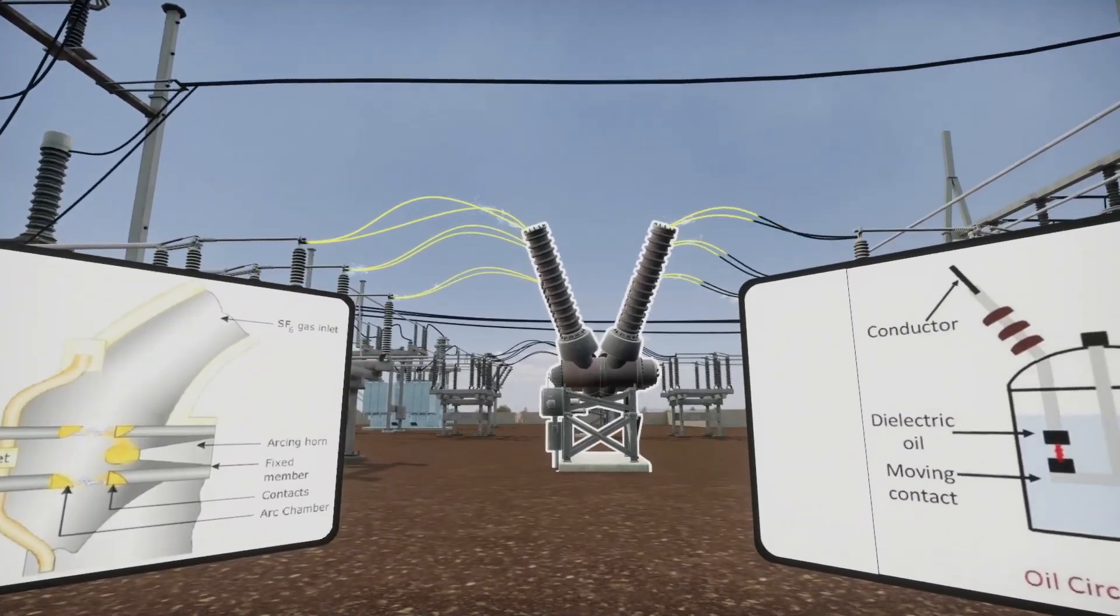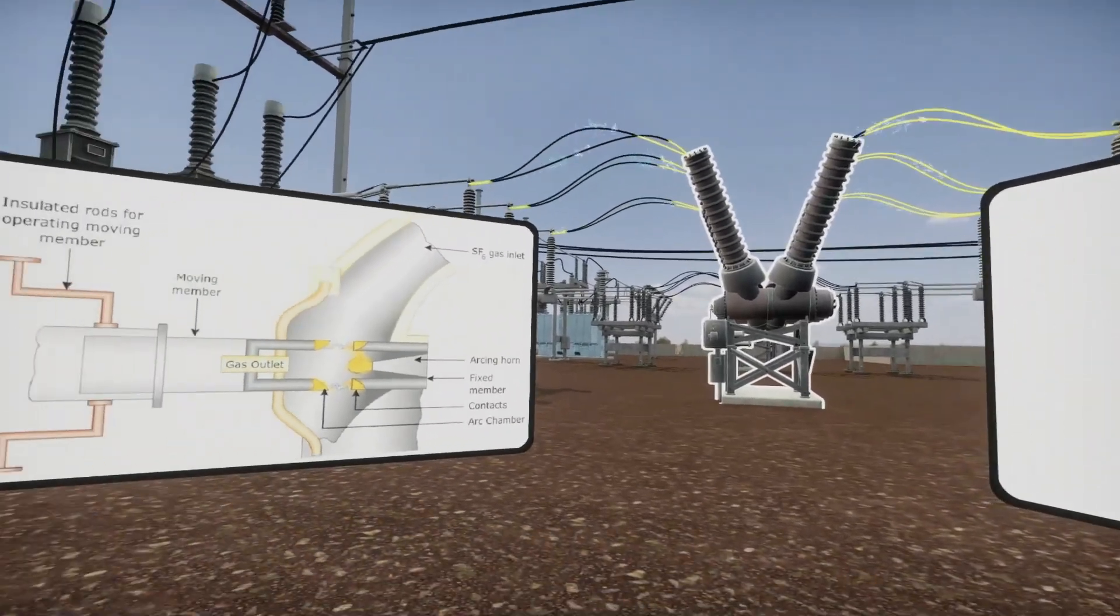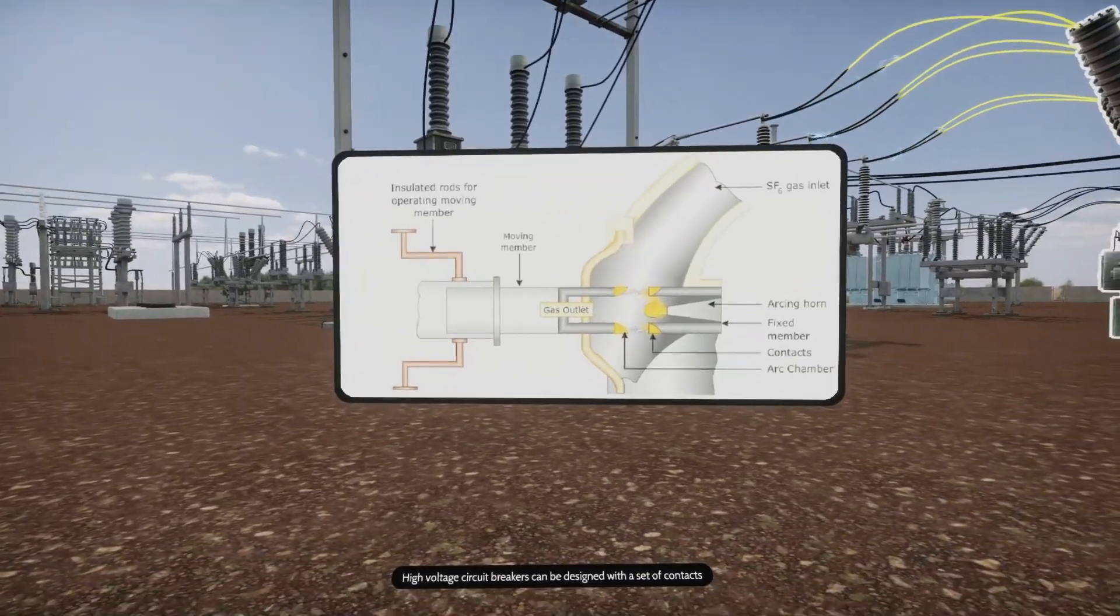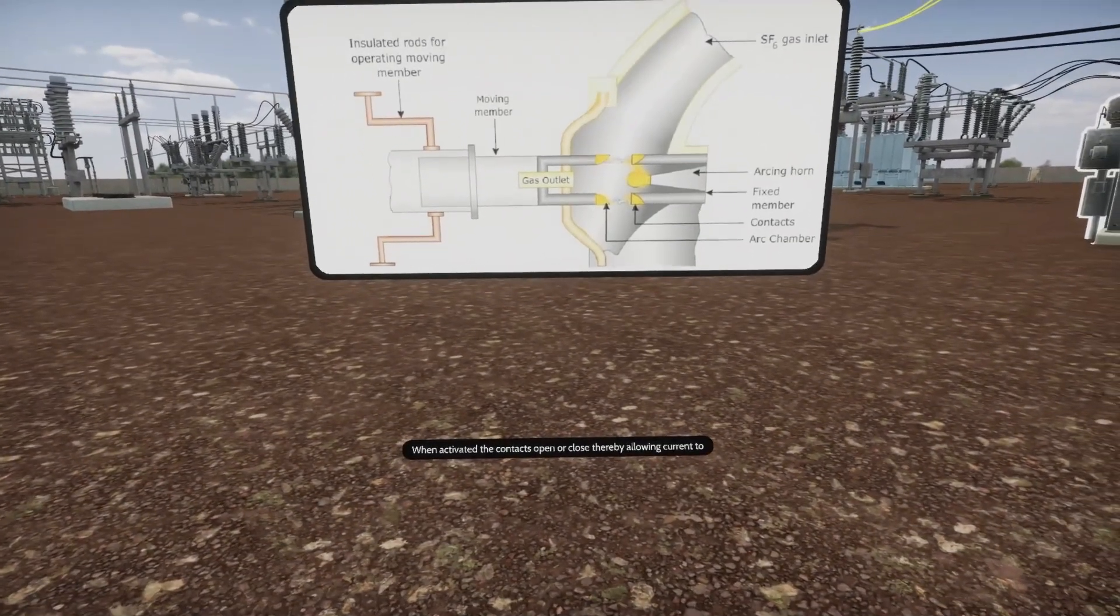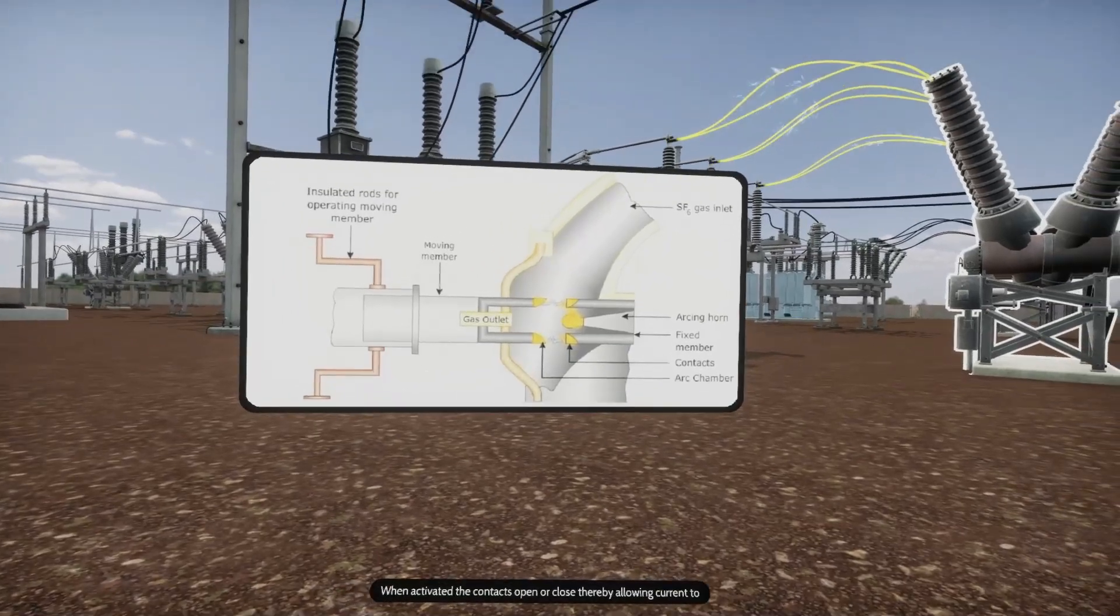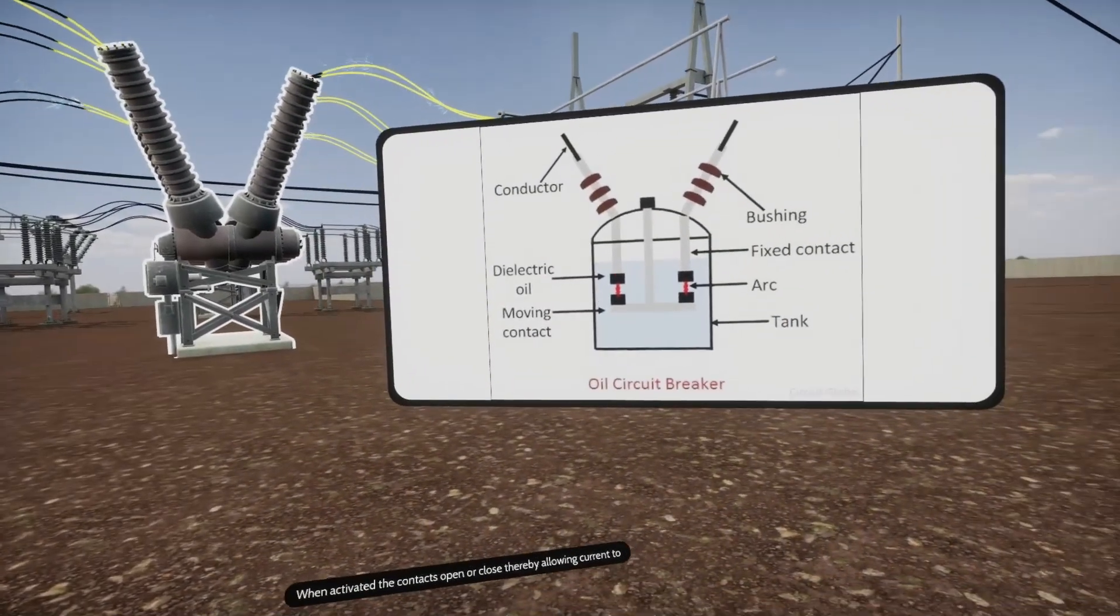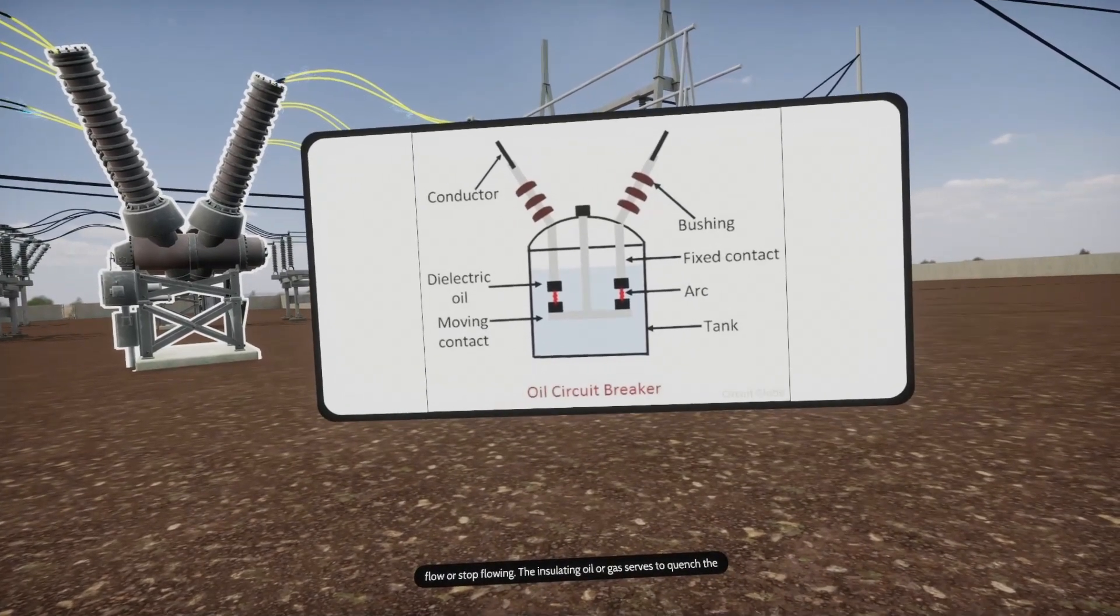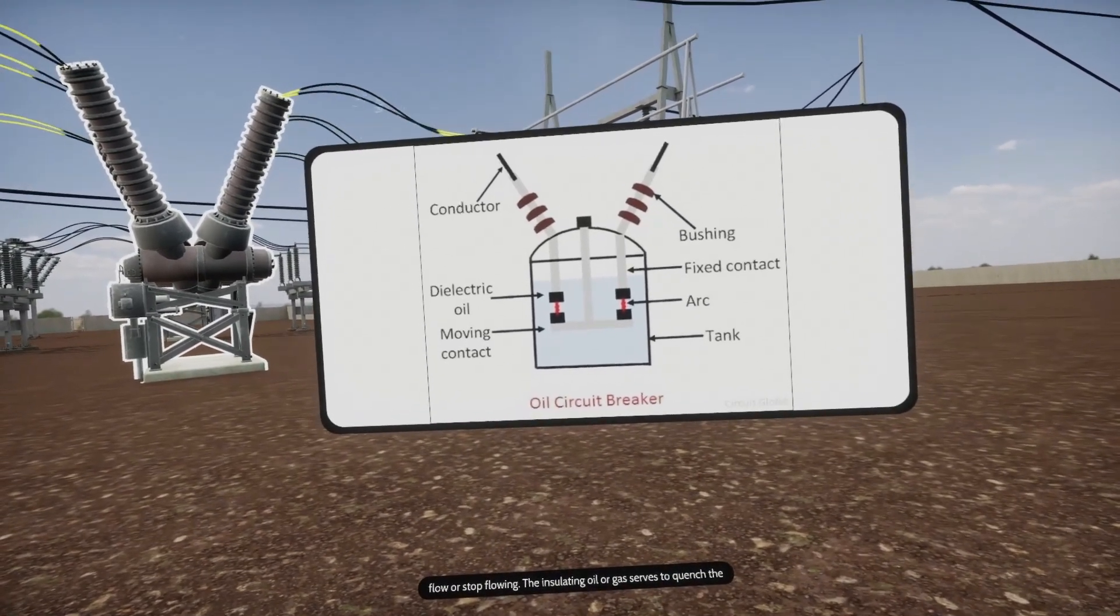High voltage circuit breakers can be designed with a set of contacts immersed in a tank filled with insulating oil or SF6 gas. When activated, the contacts open or close, thereby allowing current to flow or stop flowing. The insulating oil or gas serves to quench the arc generated by the opening of the contacts.